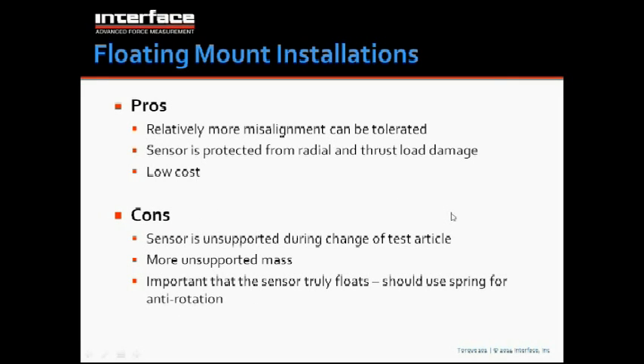Cons are the sensor is unsupported during a change of a test article. Imagine if you have a motor and a torque sensor and you want to test a bunch of different pumps. Every time you disconnect a pump, the whole drive line is going to sag. You have to support it. A pedestal style sensor would prevent that. Also, you have more unsupported rotating mass in a floating style than if you had a fixed mount.